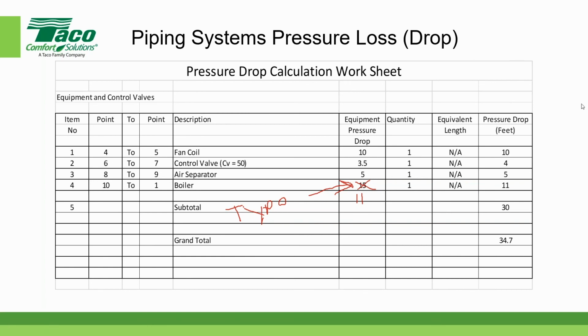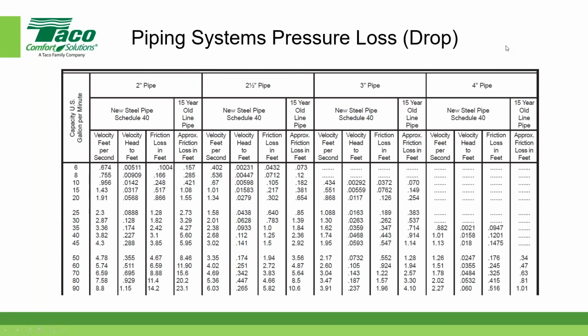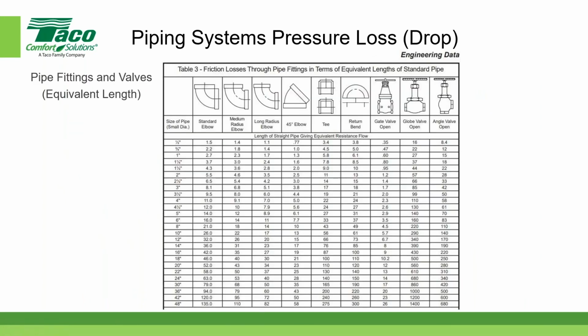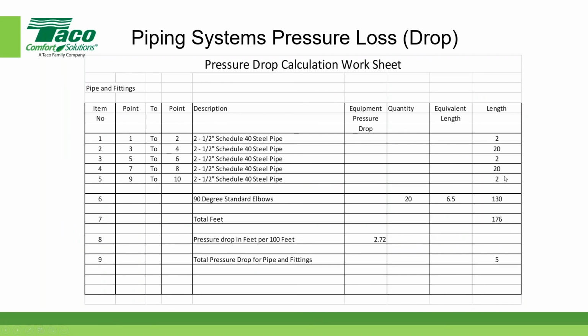Okay. How does glycol affect these calcs, or does it? Yes. So if you'll notice, let's go back here for a moment. Erase all that stuff. The table that I used for this pressure drop calculation is all based on water with a specific gravity of 1. So if you were doing pipe pressure drop calculations for, say, glycol, then all the values in the table would remain the same except for this value here. In this case, it's 2.72 based on water with a specific gravity of 1. If it was glycol, you'd use a different pressure drop in feet per 100 feet. But other than that value, all the rest of the values remain the same.